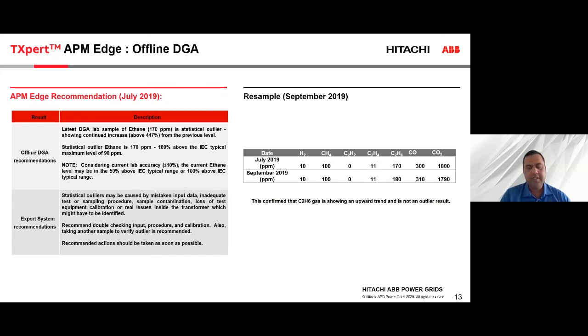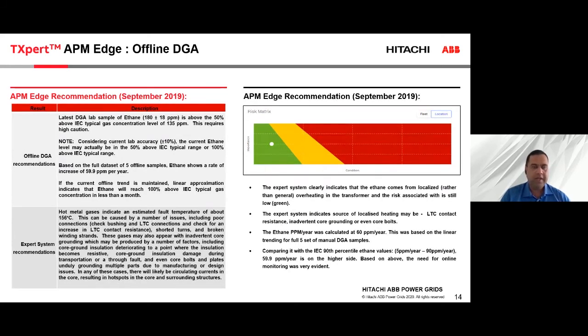And in this case, in September 2019, our offline DGA recommendation basically said that the latest sample is confirming that it is above 50% of the typical IEC gas concentrations. And we automatically did a linear interpolation, a straight line fit of the full 5 data sample sets. And it showed that ethane is going up at 60 ppm per year. And if this trend continues, our statistical tools indicated that ethane will cross 100% above the IEC typical gas limits in less than a month. So now we are able to predict in future when the gas levels will be higher than 100% above what is the typical recommended by IEC.